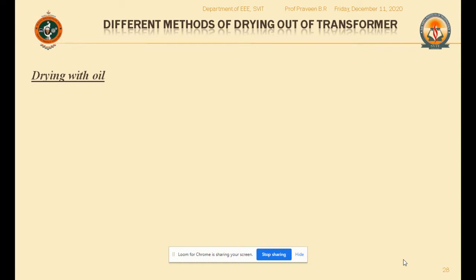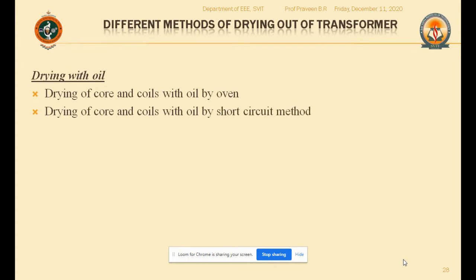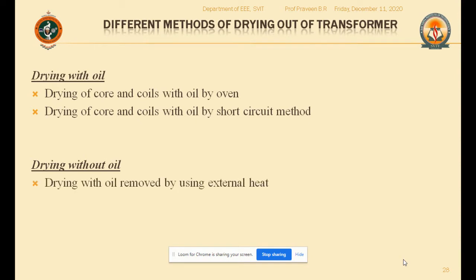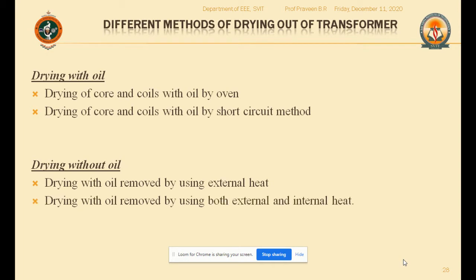One is when the oil is inside the transformer, that is, drying of core and coils with oil by the oven method, and drying of core and coils with oil by the short circuit method. These are the two methods. Without oil, when you remove the oil from the transformer tank, we have drying of the windings with the oil removed by using external heat, and one more method is by using external and internal heat.